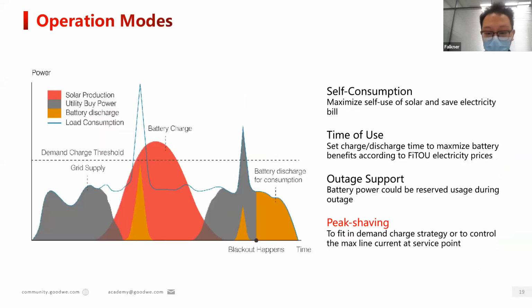Next is our new mode called peak shaving mode. In some countries, there is a demand charge, and you need to keep your load under the threshold. You can see on the left, once the load power comes to the demand charge threshold, the battery will discharge to cut off the peak, in order to save your money.